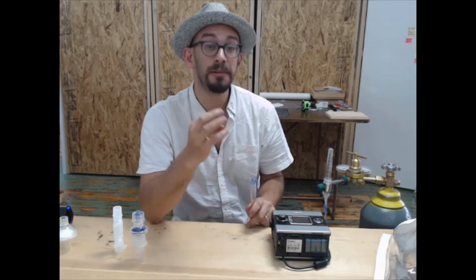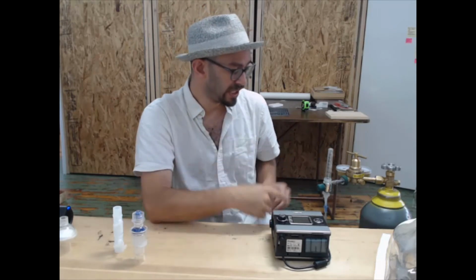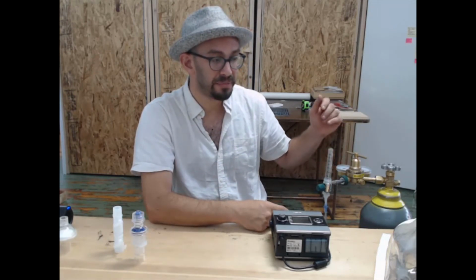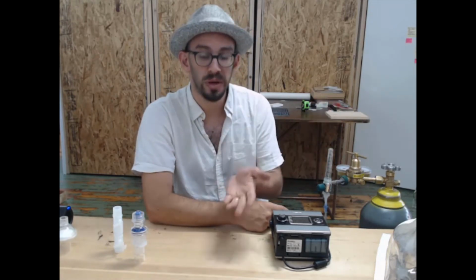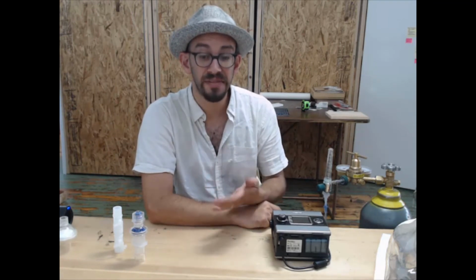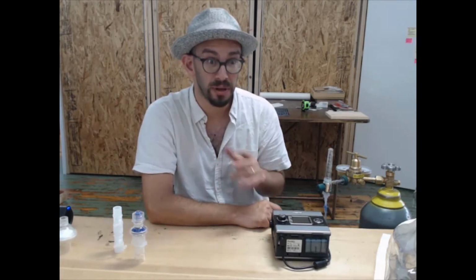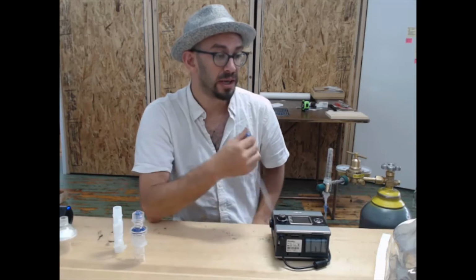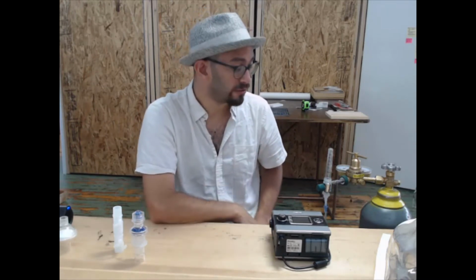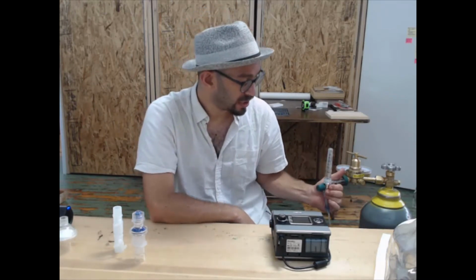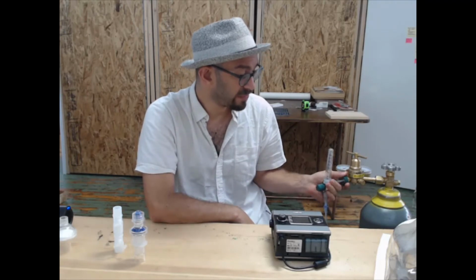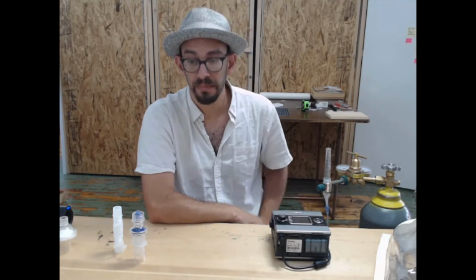And something that will be very, very convenient is the majority of tanks often have a 15 liter a minute low flow regulator. Hospitals also often have higher flow regulators. The one I have on here is a standard hospital issue one that can go up to 70 liters a minute.